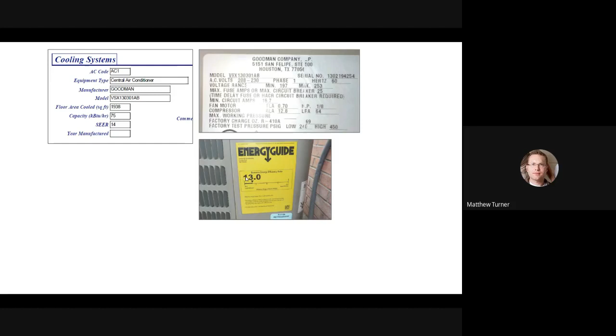Thanks for your comments, Romney. This job shows the condensing unit is a Goodman model, blah blah blah, and it indicates it's a 13 SEER with a 30,000 BTU cooling capacity. However, it was modeled as a 14 with a 75,000 capacity. The Energy Guide sticker in the photo of the unit confirms it's a 13.